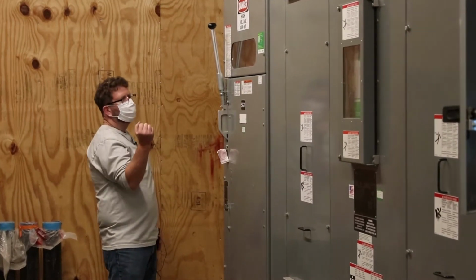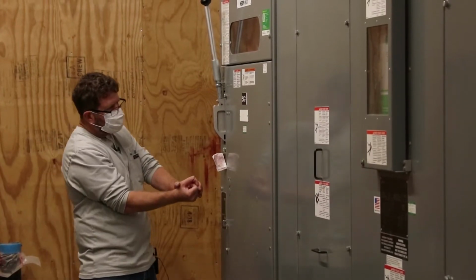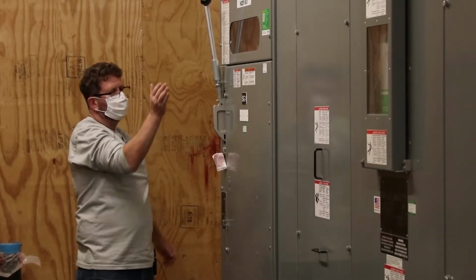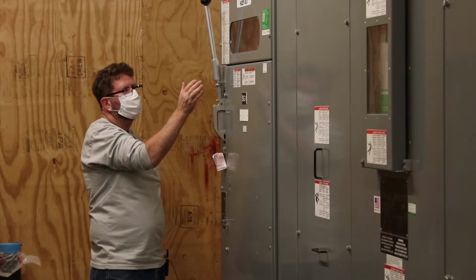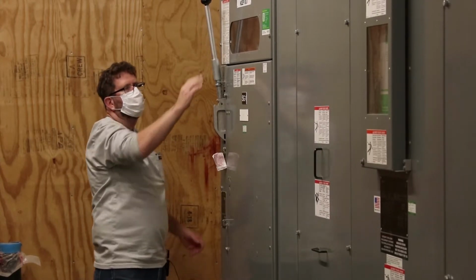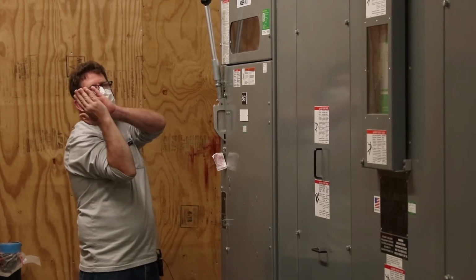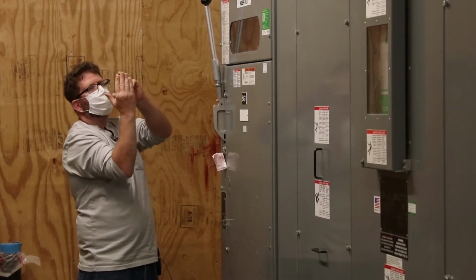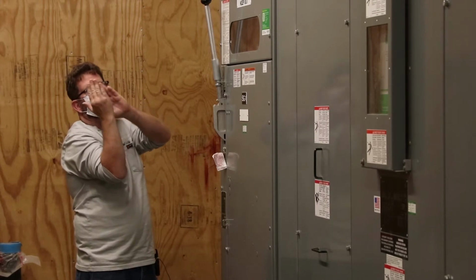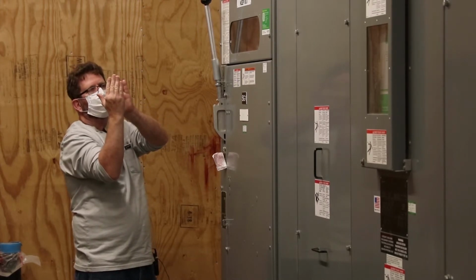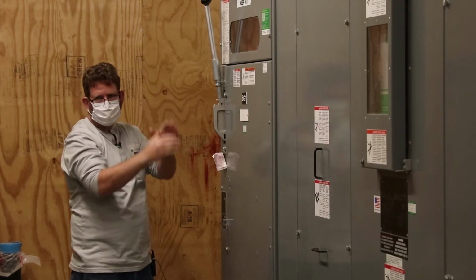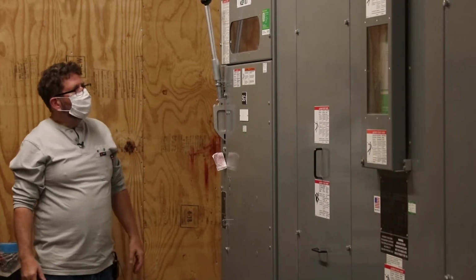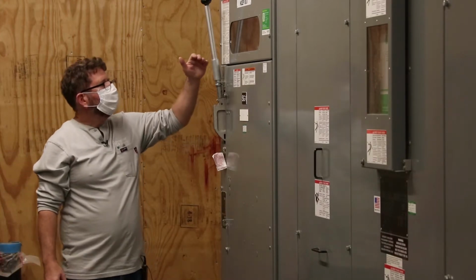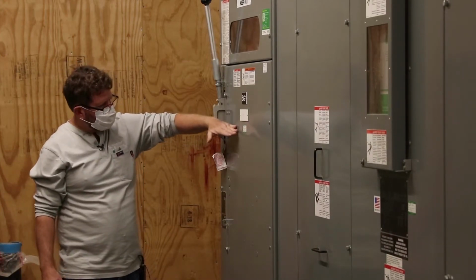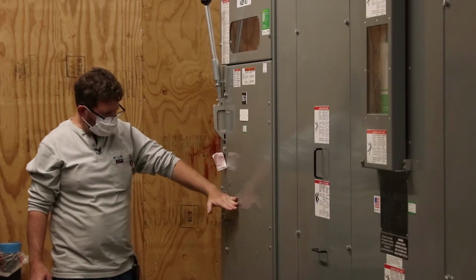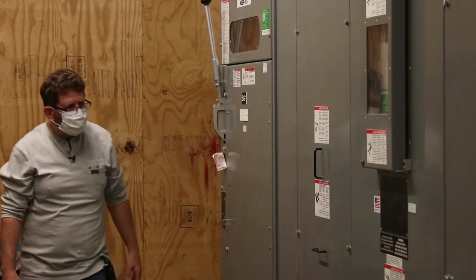You have the same over toggle mechanism. The switch handle is going to be here. You're going to bring it up. You're compressing the spring. It goes over top dead center and releases, slams the blades in. When the blades go in, the arc tip and the main blade go in together. Inside the arc chute, there's electrical contact out further, so it's going to make electrical contact in the arc chute before the main blades make up. And below the main switch is the fuses, and you have cable connections over to the transformer.